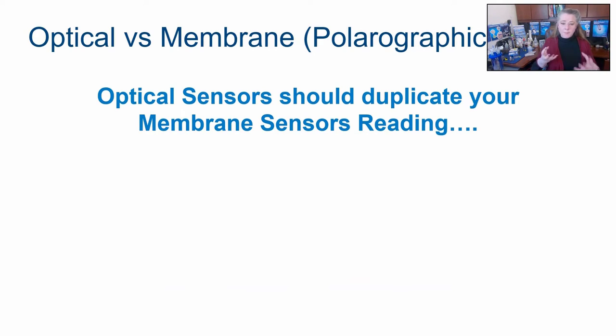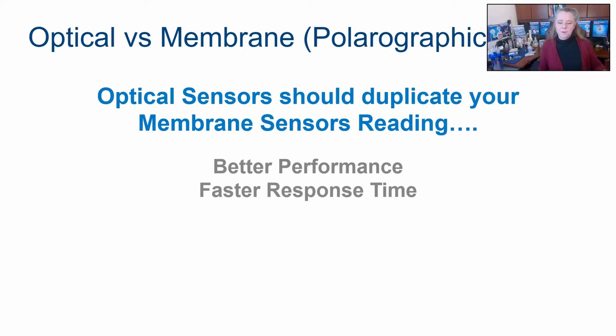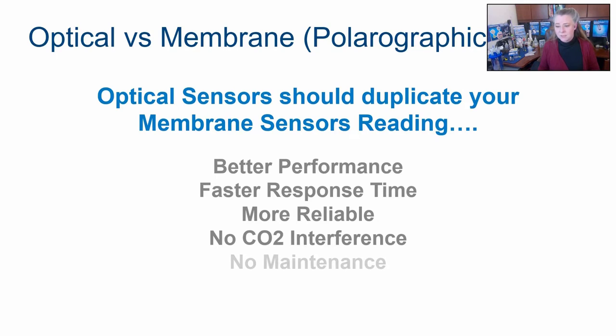So in theory, optical sensors should be the same. They should give you the exact same measurements as membrane sensors. But in reality, they give you the same numbers, but their performance is a little bit better. There are fewer things that can impact the performance, like the electrolytes and things like that. They're faster in response time than polarographic, and they tend to be more reliable and better for longer reactions because you don't have to worry about CO2 fouling after a few days. No CO2 interference. And the maintenance. Remember, polarographic, lots of maintenance. This, replace a cap. I'm lazy. I can tell you which one I like.